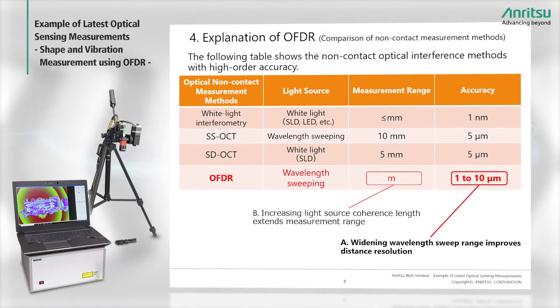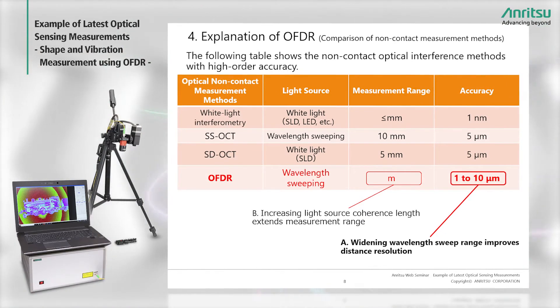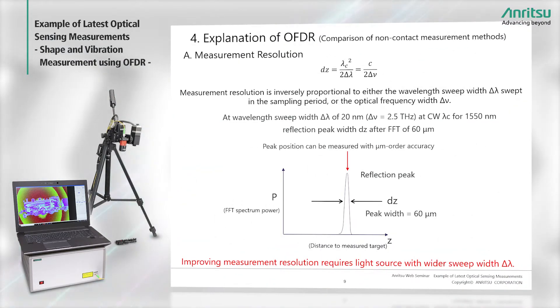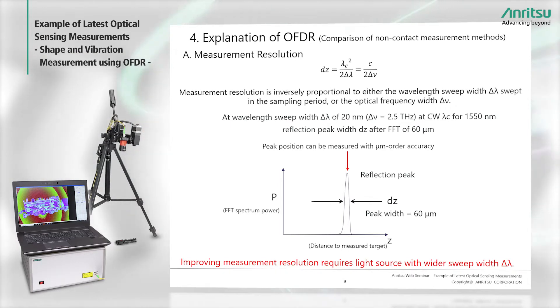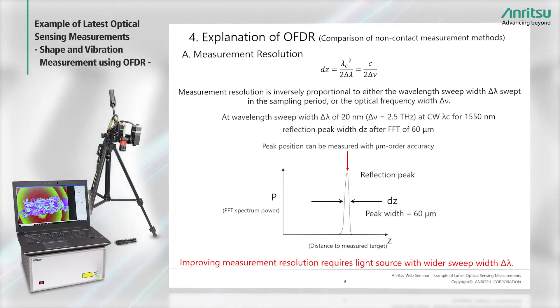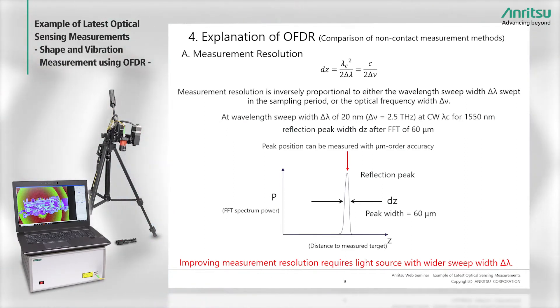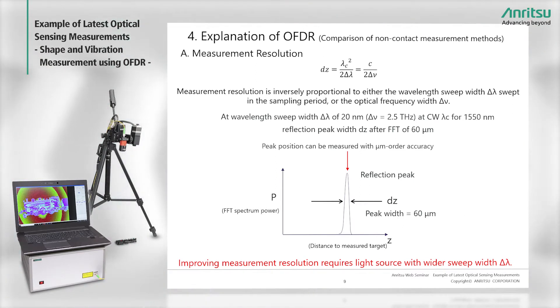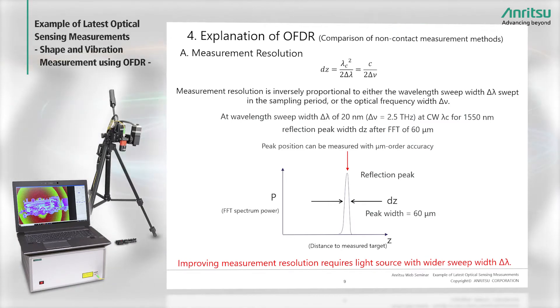Returning to the previous slide, I'll explain why widening the light source swept wavelength range improves distance resolution. The peak width DZ after FFT processing is inversely proportional to either the light source wavelength sweep width delta-lambda or the light frequency delta-nu. For example, at a center wavelength of 1550 nanometers with a wavelength sweep width of 20 nanometers, the peak width DZ is 60 micrometers — the measurement resolution. When the wavelength sweep width delta-lambda is doubled to 40 nanometers, the peak width DZ is halved to 30 micrometers, improving precision. This is how widening the wavelength sweep width improves measurement resolution.